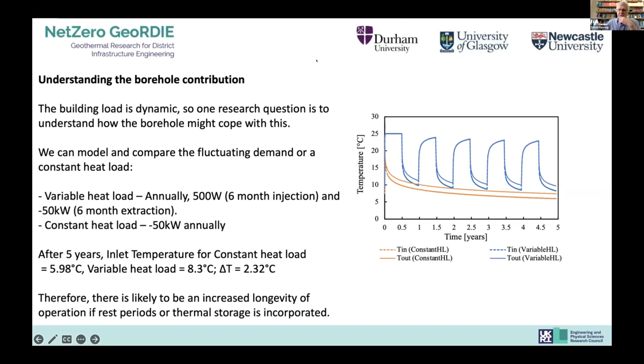Using this approach, we're conscious that the building load is dynamic, so we can compare the requirements of the building between low demand in the summer and high demand in the winter. If we assume constant load, we get these orange curves where the system is losing temperature, the well getting to a lower and lower temperature as time goes on, so in 5 years it is at its lowest temperature. But with the fluctuating load, that gives the well a bit of a rest, resulting in a slower reduction in temperature, and so the longevity of the resource has increased.